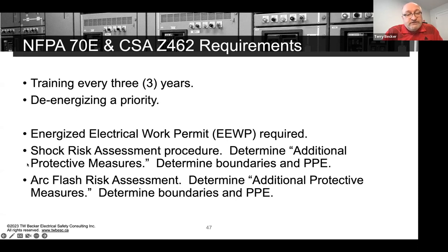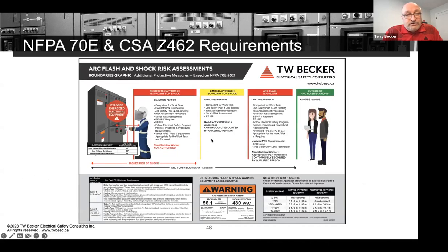We have the shock risk assessment and the arc flash risk assessment to get boundaries and the PPE. So we've got two shock protection approach boundaries, limited and restricted, and one arc flash boundary. And again, this graphic I use is just simply to communicate these boundaries are used to control keeping unqualified, unprotected workers out. The workers that are qualified and authorized, that's in them, have on arc flash and shock PPE. So there's different rules and policies and controls that are required depending on which boundary is breached.